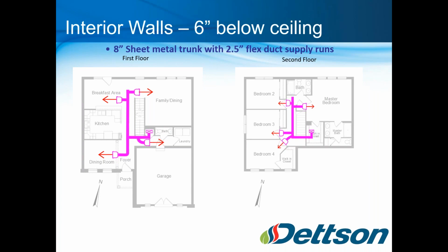So, our installs are based on bringing everything to the interior walls of the house, cutting back on that sheet metal work, going all the way to the exterior walls. So interior, 6 inches from the ceiling. Our first rule of thumb is we try and get everything bathing the window. If we can't do that, then we will go parallel to the window, etc. So we've got a couple of rules to follow, but we're running off of 6-inch or 8-inch mains, and the smart ducts are 2.5-inch flex ducts.